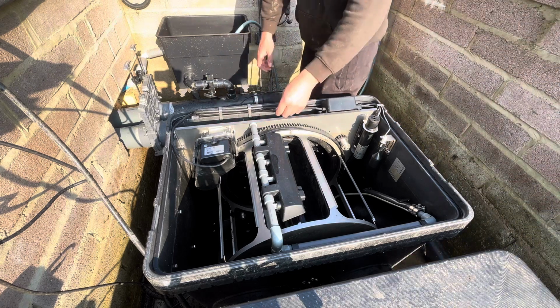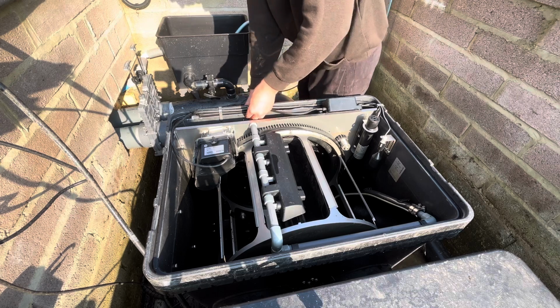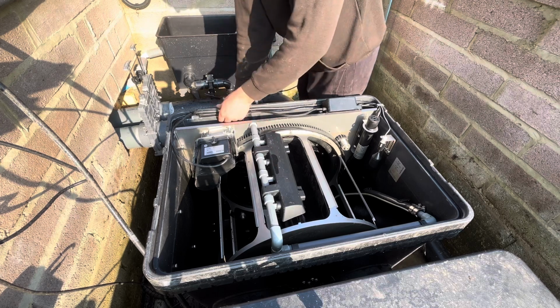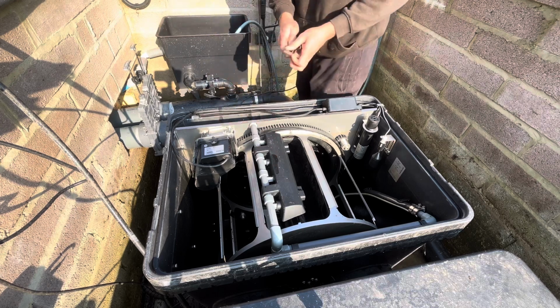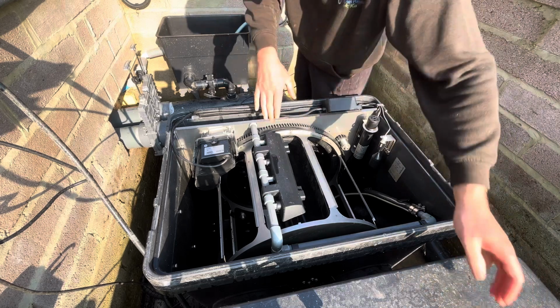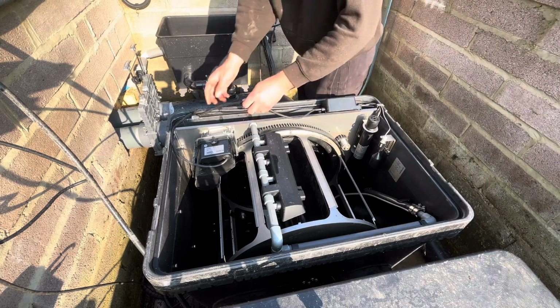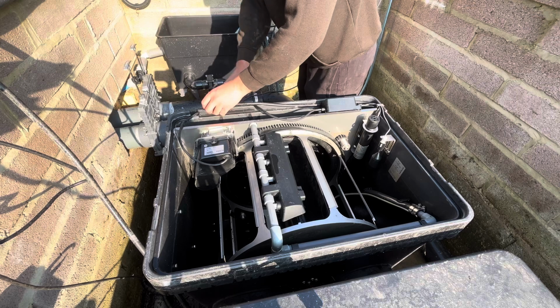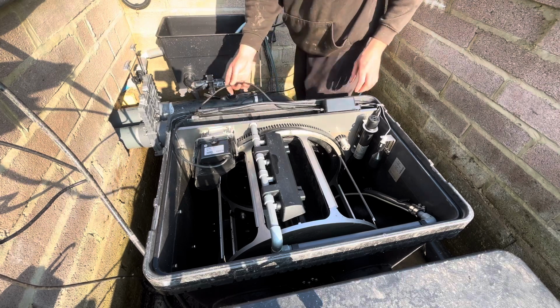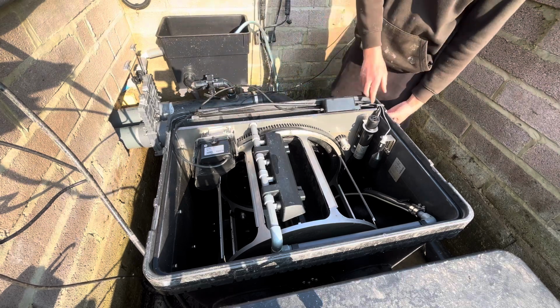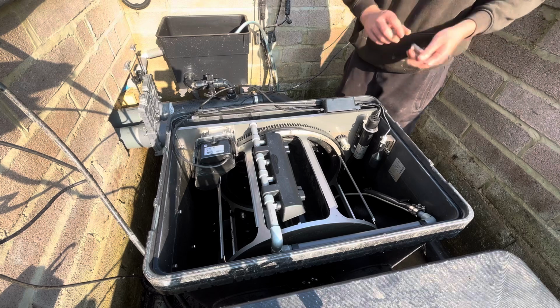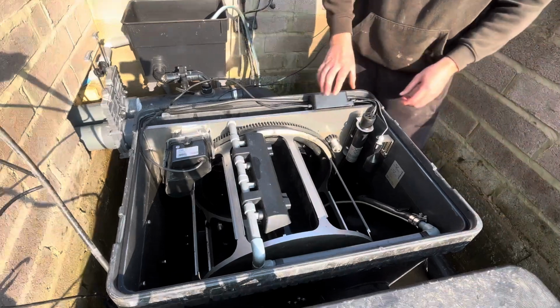Right, these cables go to the sensor, so we just need to remove these cable clips. They are purely just to keep all the cable tidy, make sure no cables get caught up in the drum or anything. So we'll remove, it's this thinner one that goes to this box here. We've then got another cable clip there, so we'll remove that.